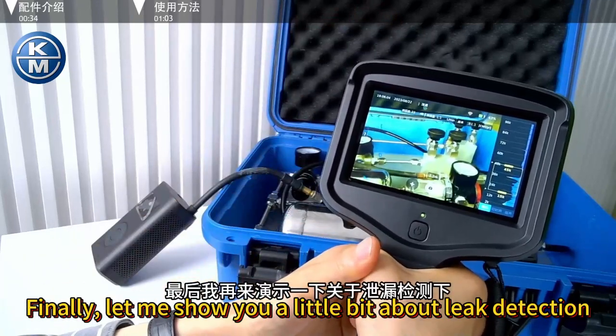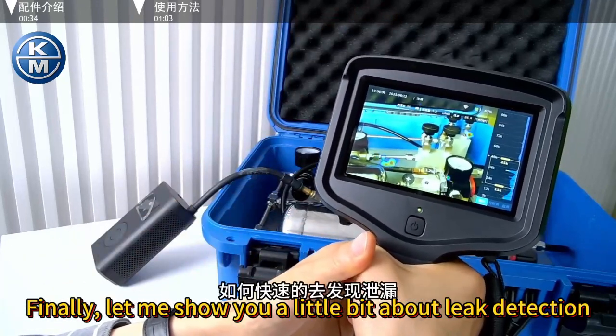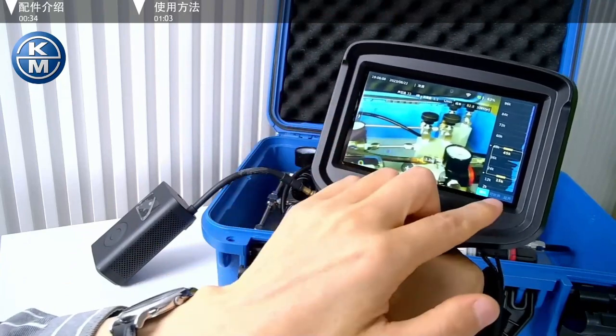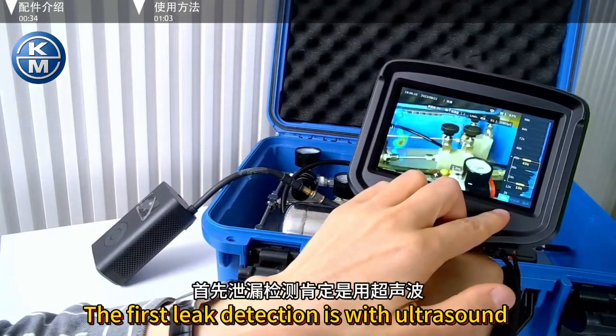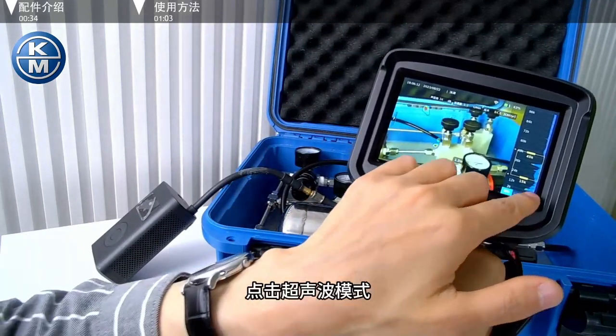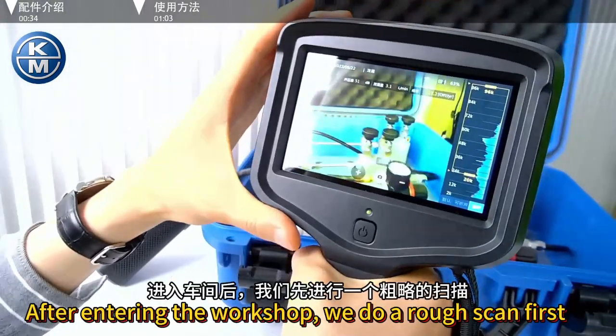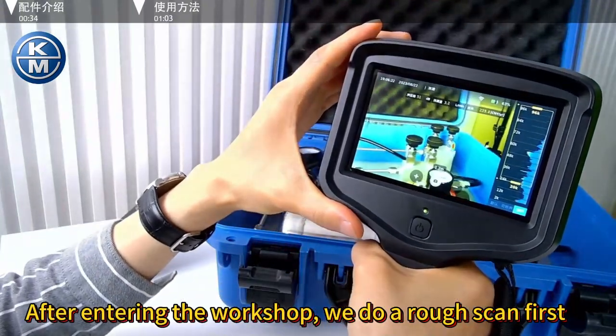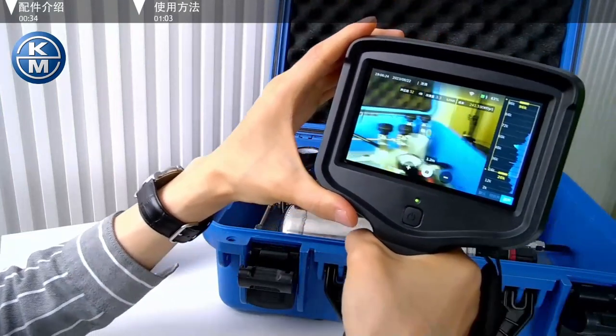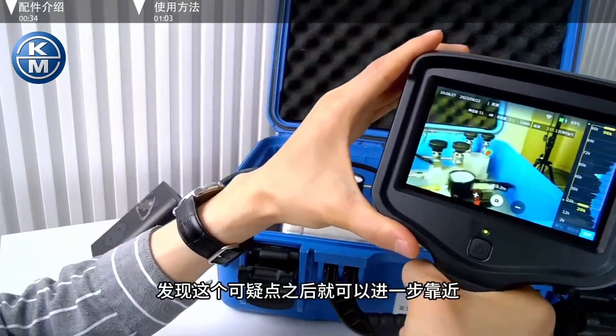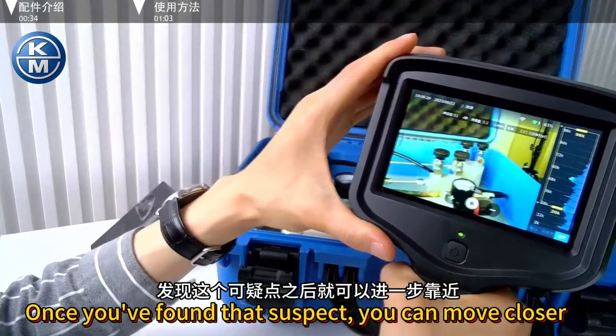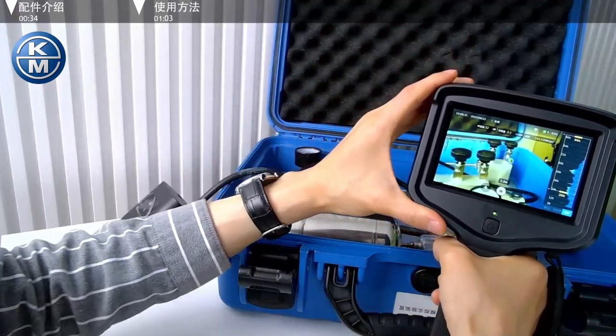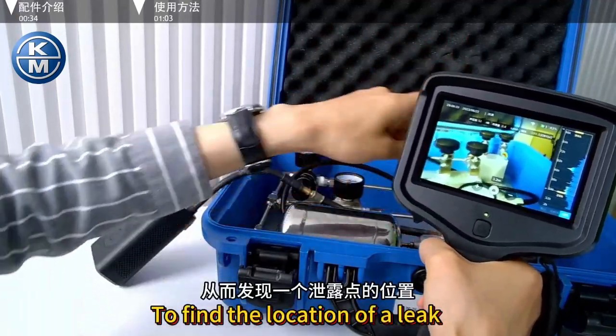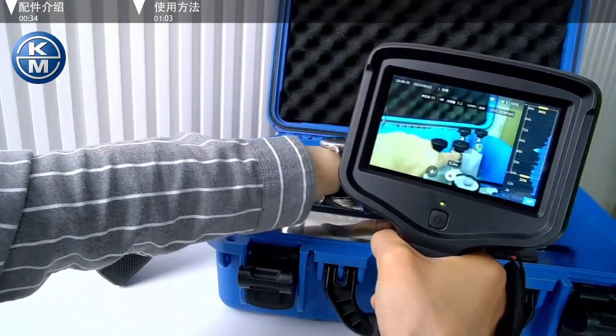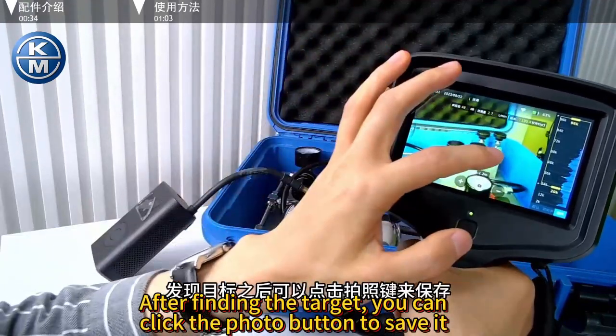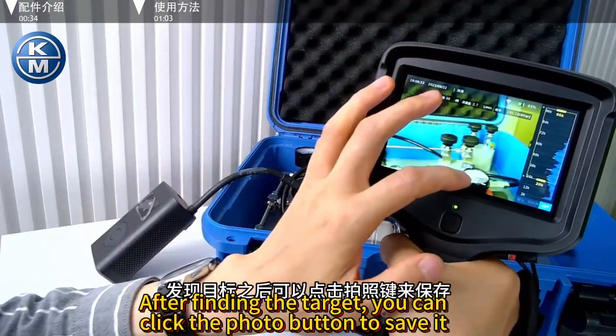Finally, let me show you a little bit about leak detection, how to find leaks quickly. The first leak detection is with ultrasound. Click ultrasonic mode. After entering the workshop, we do a rough scan first. Once you've found a suspect, you can move closer to find the location of a leak. After finding the target, you can click the photo button to save it.